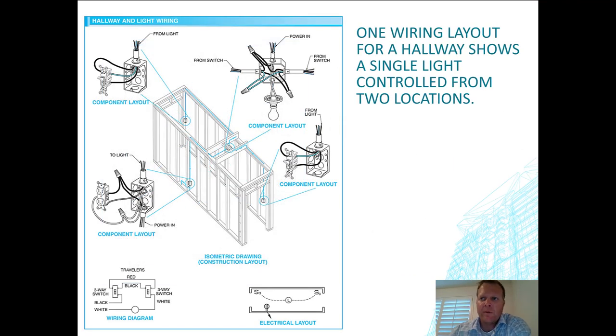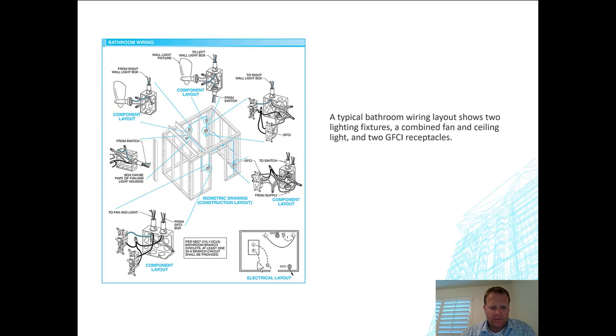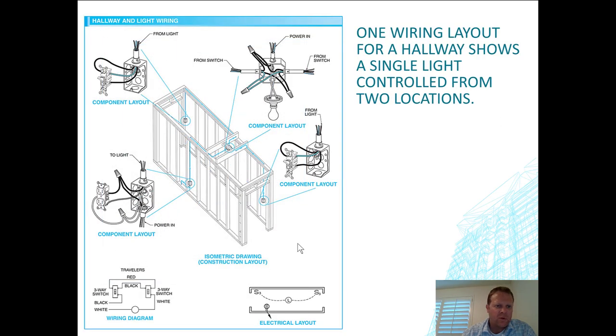Looking at the floor plan for the bathroom — switch one for the light, switch two for the fan, another switch for the wall fixtures, GFCI outlets. Now here's a fun one: a three-way switch in a hallway controlling a light. Power comes in, goes up to the light, then goes two directions connecting the three-way switches.